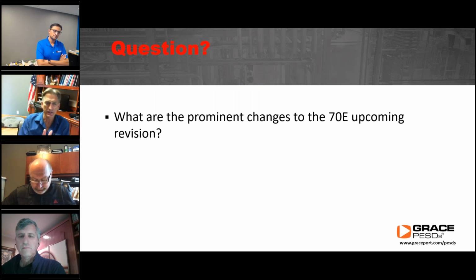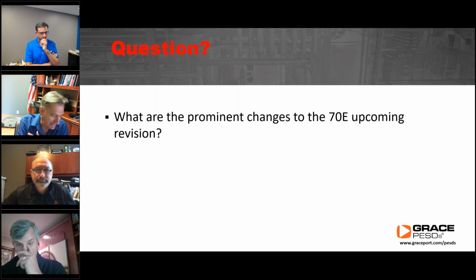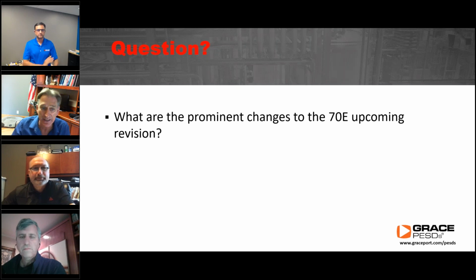In 120.5, on verifying and establishing an electrically safe work condition, section 120.5(7) tells us to use an adequately rated portable test instrument. The word 'portable' was added back in the 2018 edition, so that's not new, but now it says to test each phase conductor and circuit part—previously it said to verify it is de-energized, but now it will say to test each conductor and circuit part for the absence of voltage.